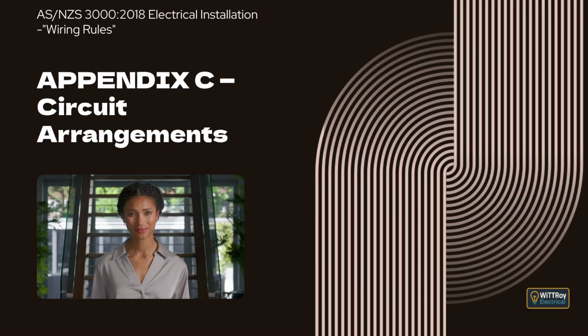Clause C6.2. Basis of calculations. This clause explains that the number of cables that may be installed in a circular enclosure is determined by comparing the internal cross-sectional area of the enclosure with the cross-sectional area of the cables, and then applying a space factor. The space factor allows for the way cables pack together and recognizes that cables and enclosures are circular rather than square. Different space factors are used depending on whether one cable, two cables, or three or more cables are installed together. The calculation method is demonstrated using common conduit and cable combinations.